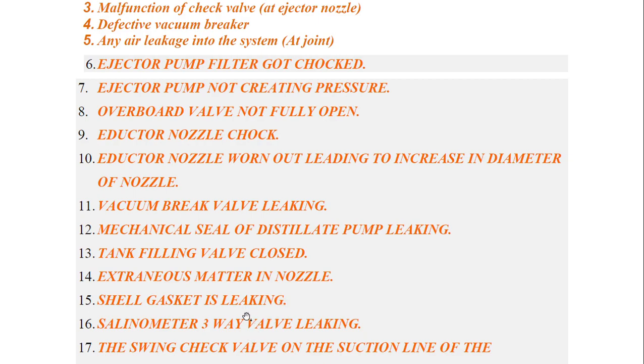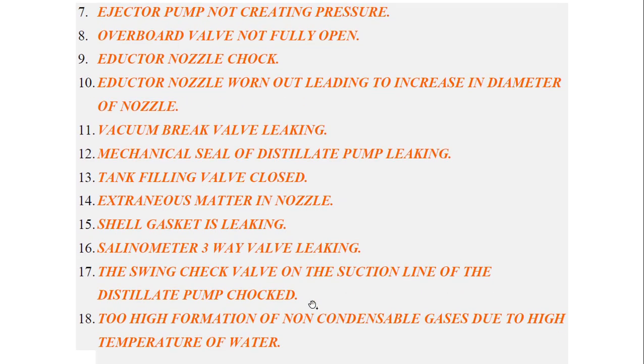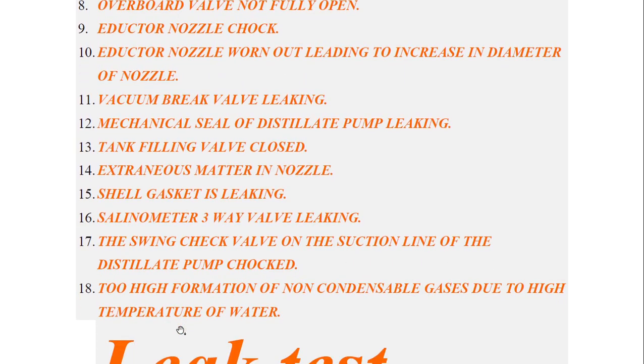Foreign particles or deposits can be present in the shell. Shell gasket leaking — this is an obvious reason; if the gasket leaks, the vacuum will fail. Salinometer three-way valve leaking — there is a three-way valve in the salinometer that can be leaking. The swing check valve on the suction line of the distillate pump choked.